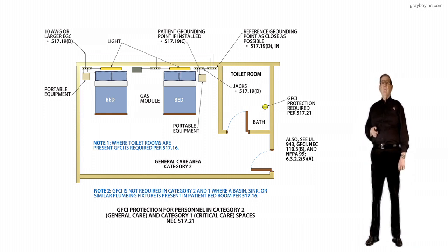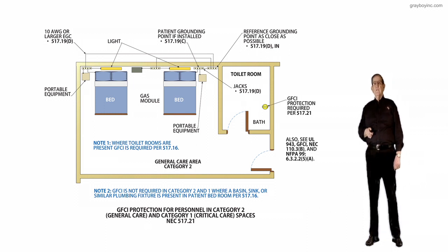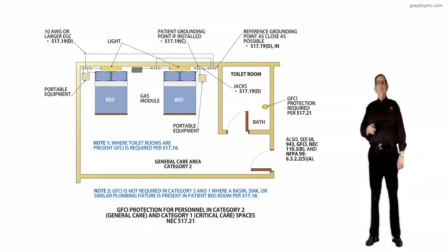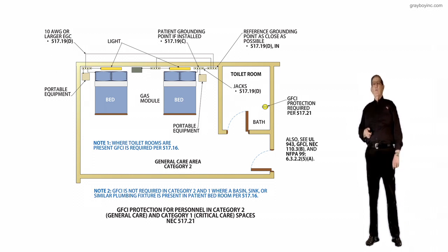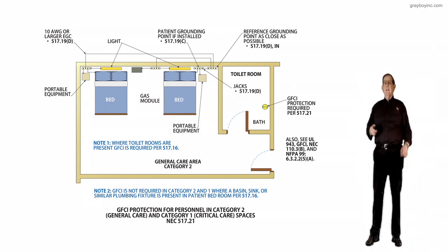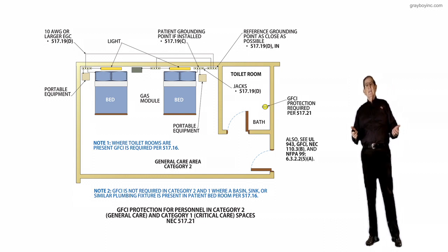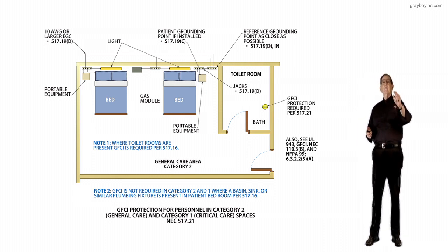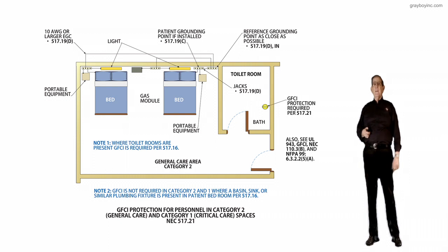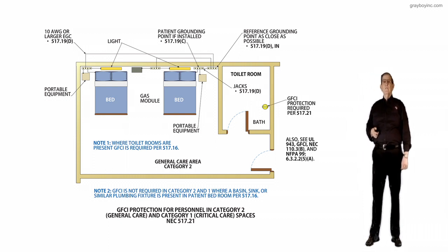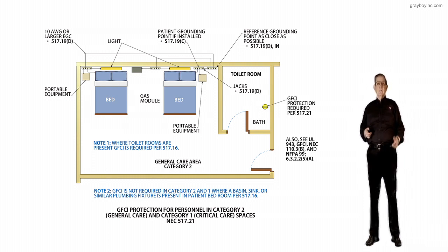And then, of course, you see the portable equipment that's cord and plug connected into the reference grounding point. Now, years ago, the metal studs that were framing members, windows, doors, and all that, we would take a number 8 solid conductor and we'd lay it across and bond and ground all that in so that it was more of an equal potential plane of the grounding.